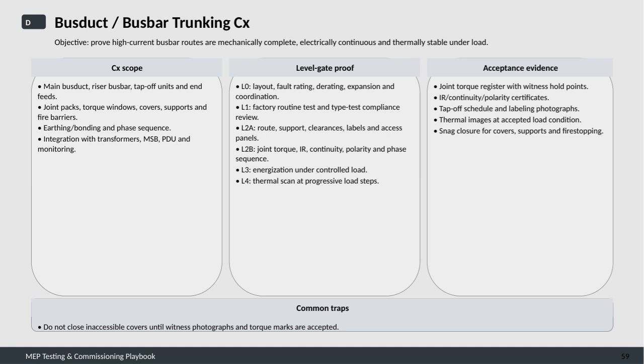We also check joint packs, torque windows, cover supports, fire barriers, earthing and bonding, as well as phase sequence. It's important to ensure proper integration with transformers, main switchboards, power distribution units, and monitoring systems. To guide this process, we follow a series of level gates. At level 0, we review the layout, fault rating, derating factors, expansion, and coordination requirements. Level 1 involves reviewing factory routine tests and type test compliance.